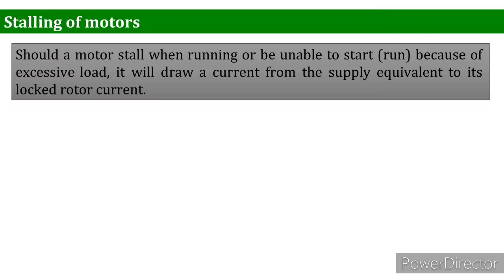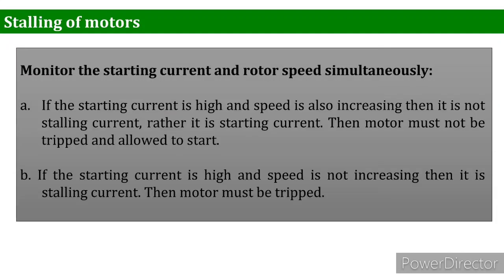So there are two conditions we will discuss about the stalling of motors, and graphs also. In the first condition, we monitor the starting current and rotor speed simultaneously. A: if the starting current is high and the speed is also increasing, then it is not a stalling current. Rather, it is a starting current, and the motor must not be tripped and must be allowed to start. B: if the starting current is high and the speed is not increasing, then it is a stalling current, and the motor must be tripped.